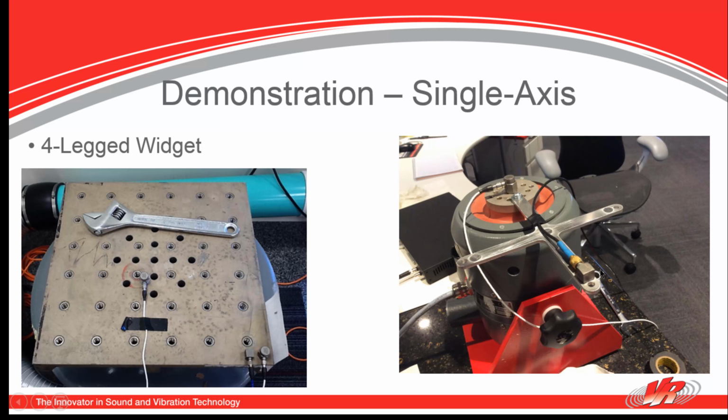I know this is a triax, but if we just compare its up and down vibration to the up and down vibration of the shaker head, might be kind of like this. If I had a full head expander, how is the outside corners vibrating compared to the center? Let's see how these vibrate, and are they in sync, and what kind of coherence values you get.